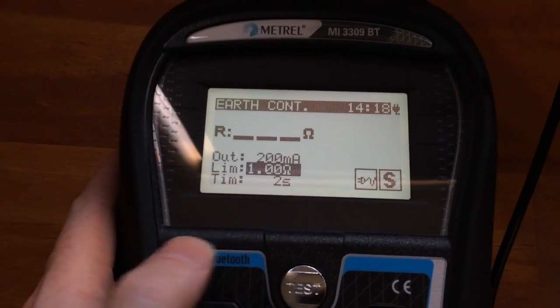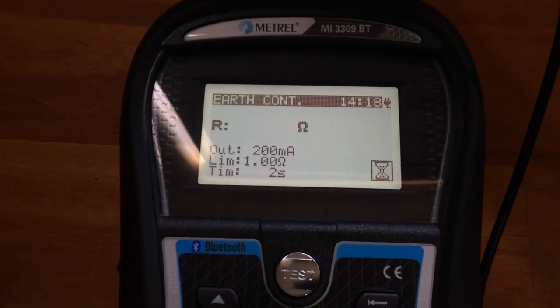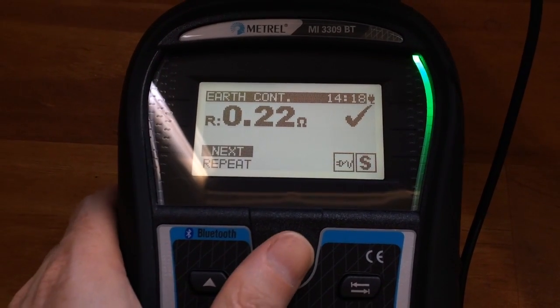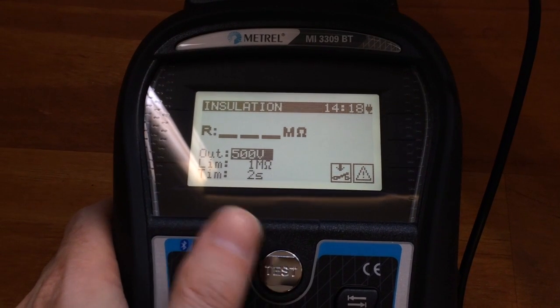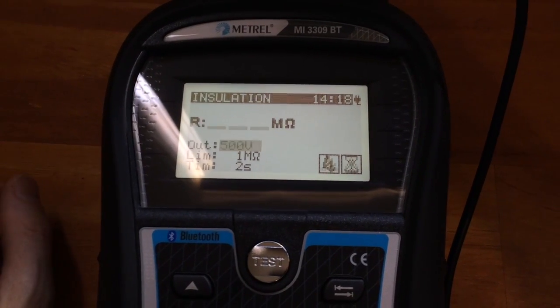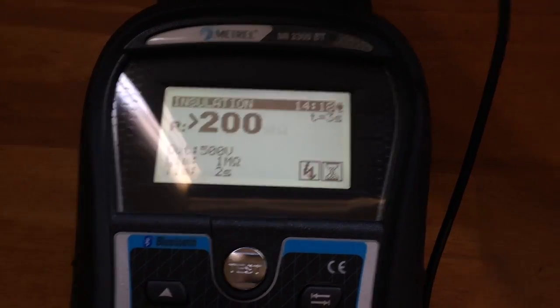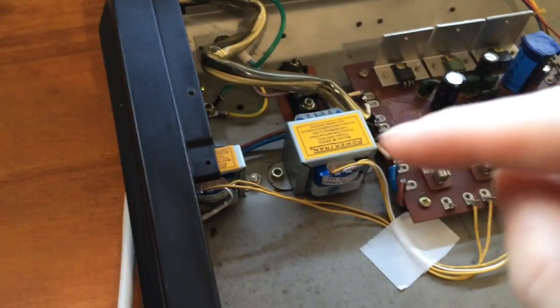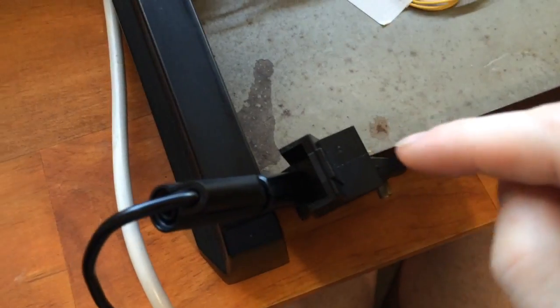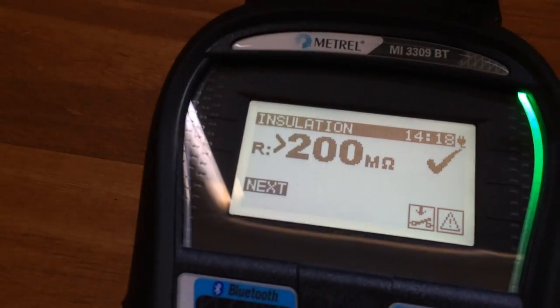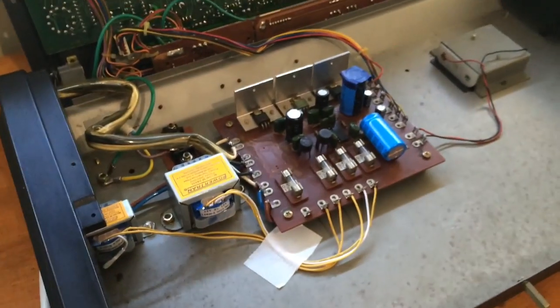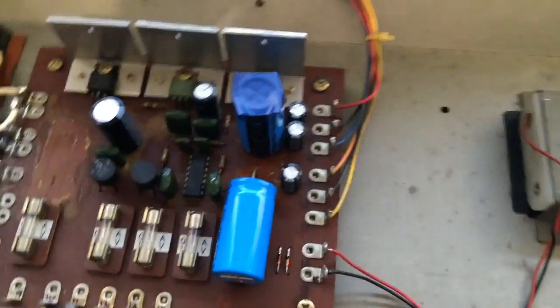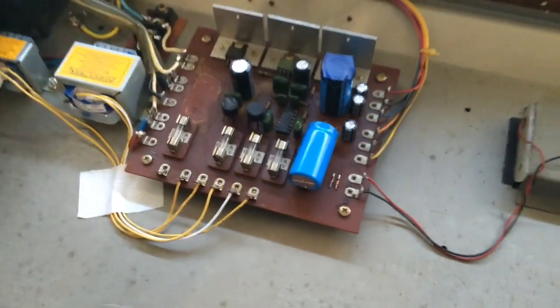Earth continuity is 0.2 ohms, so we have an earth. And then next an insulation test. This one puts 500 volts down both the active and neutral wires and then checks to see that none of that voltage makes its way to the case. So that's greater than 200 mega ohms resistance, so that's passed too. So I can turn it on now and test the outputs of the supply, and I'll show you how to do that.